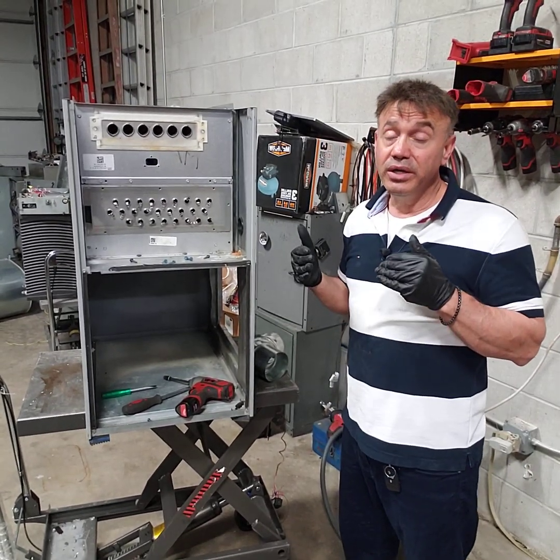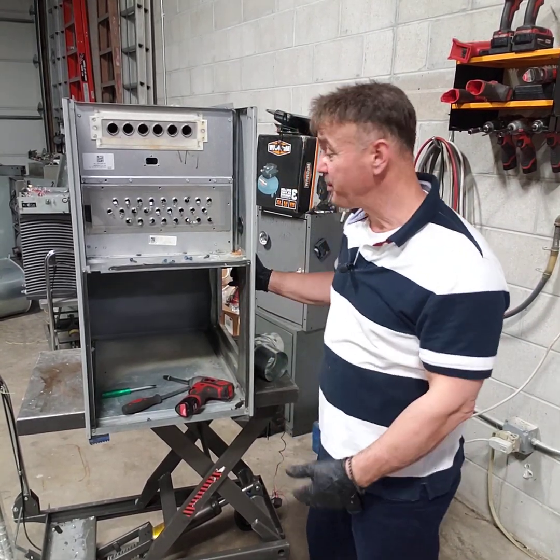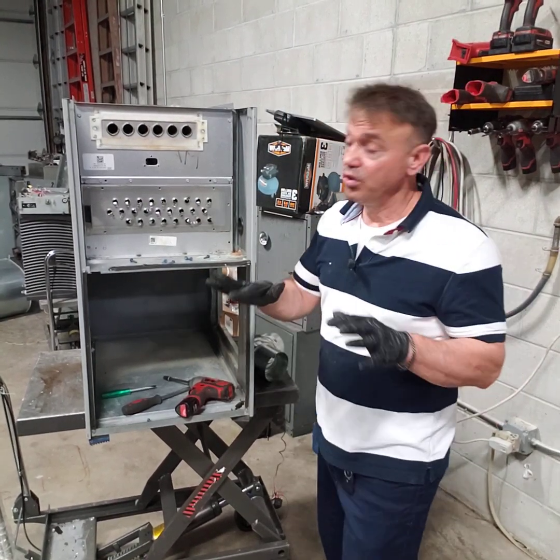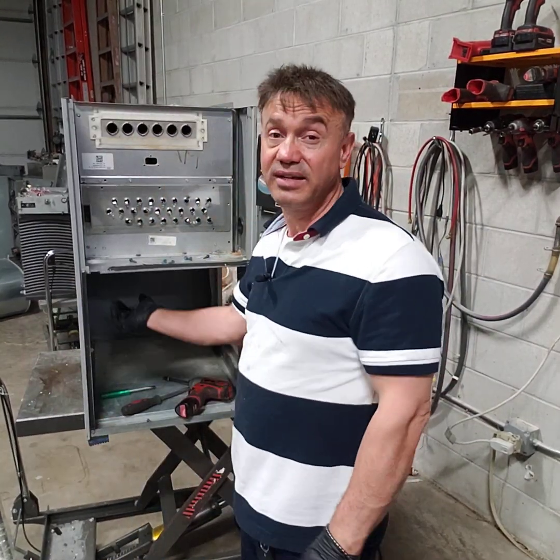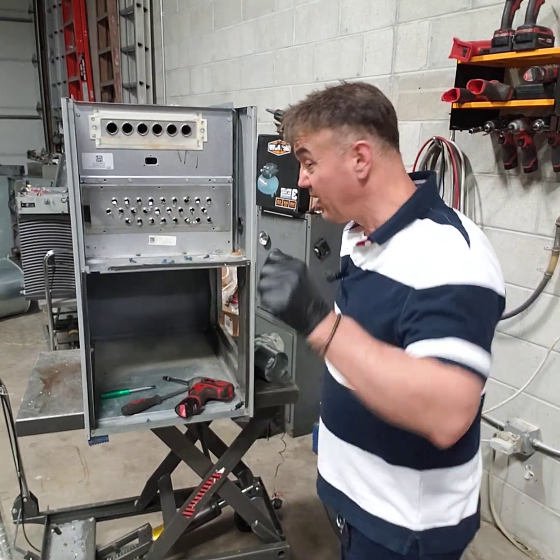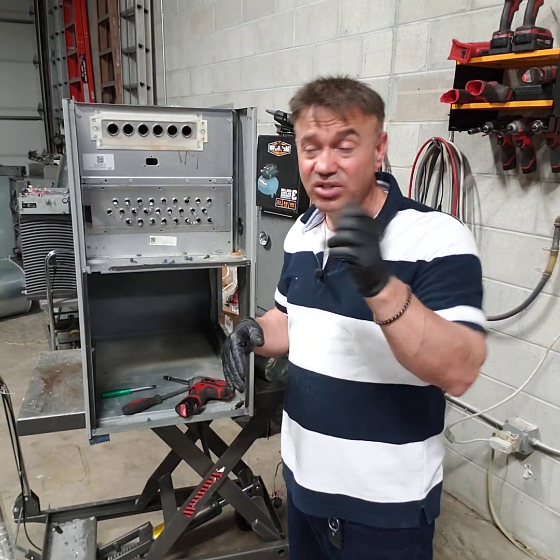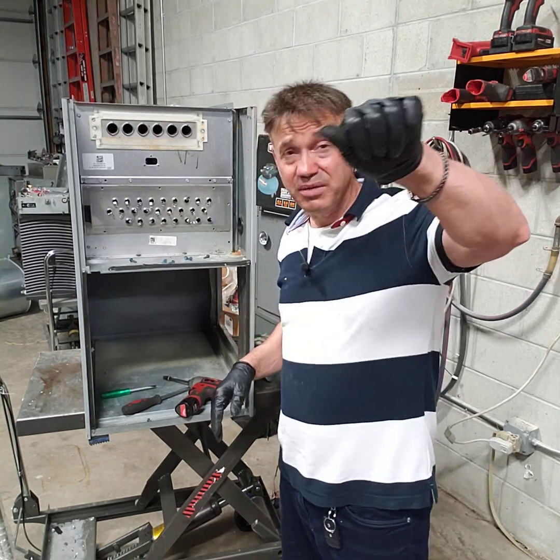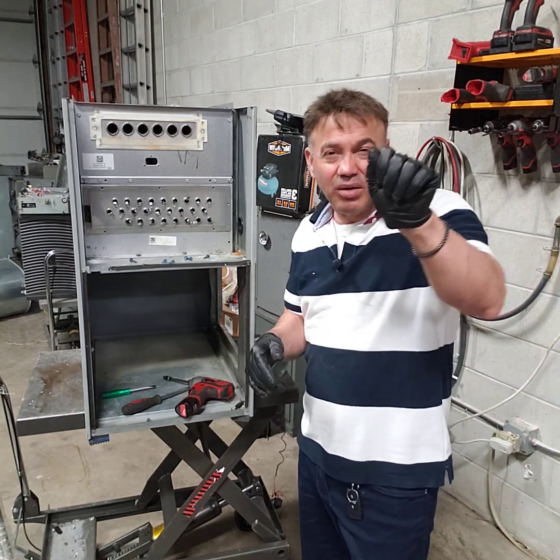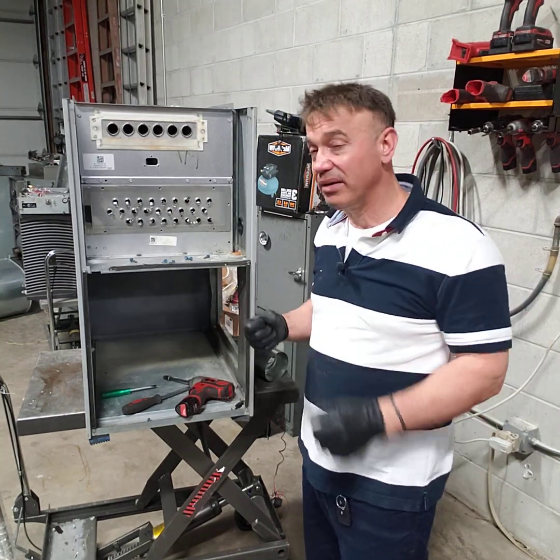But technicians or homeowners, if you go to a job and the limit switches keep tripping and the furnace is overheating, it's either the heat exchanger here is dirty. Unfortunately, you have to remove the blower. Usually I used to lay down with my head facing it. I put on a mask and glasses because dirt's gonna go in your eyes. It's a dirty job. And then I get a brush and I clean it. Sometimes it's easy, just like dust. You see a layer, and sometimes you can peel it with your hand like you're peeling a small carpet from the place. It depends. If it's in the kitchen, they're cooking all the time, so it's oil, and it's gonna be a little bit difficult.